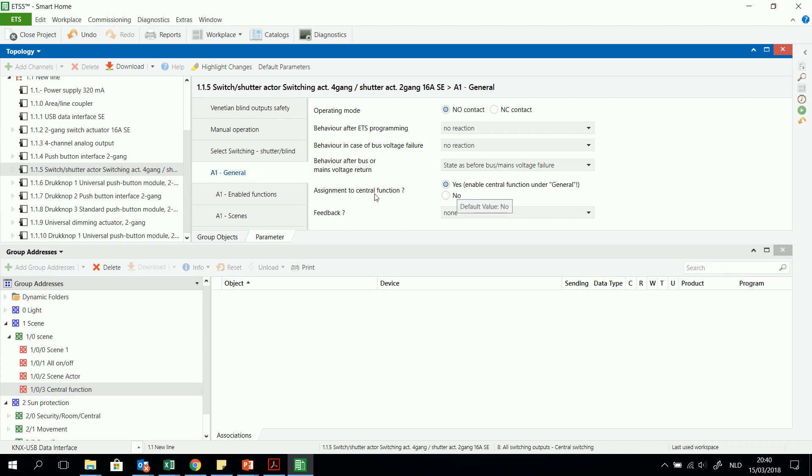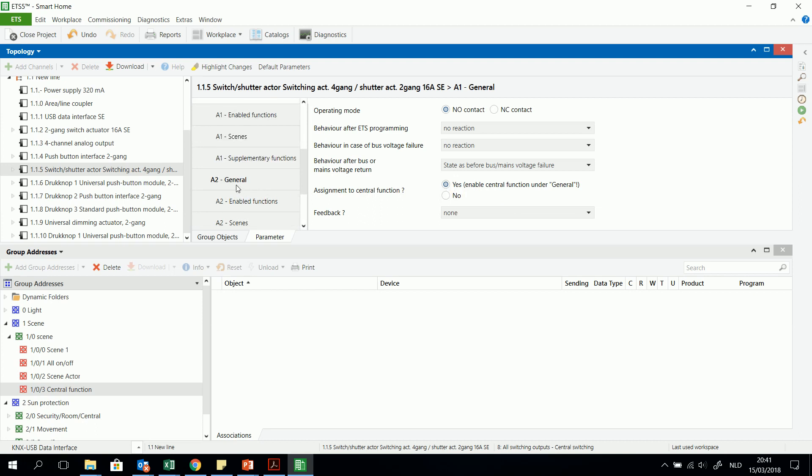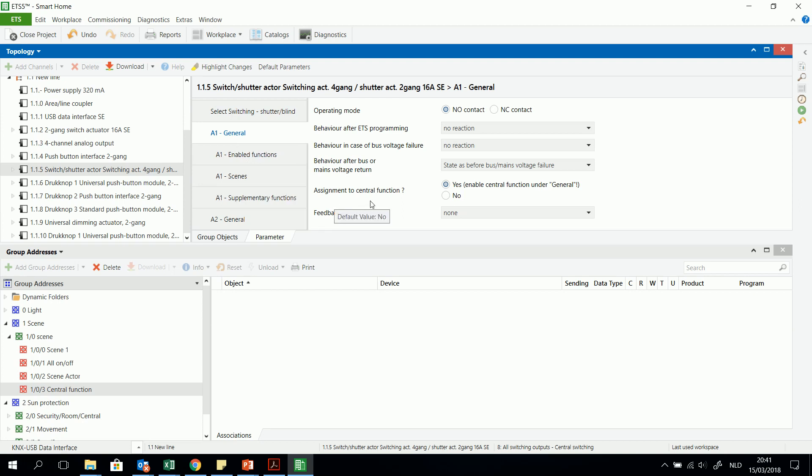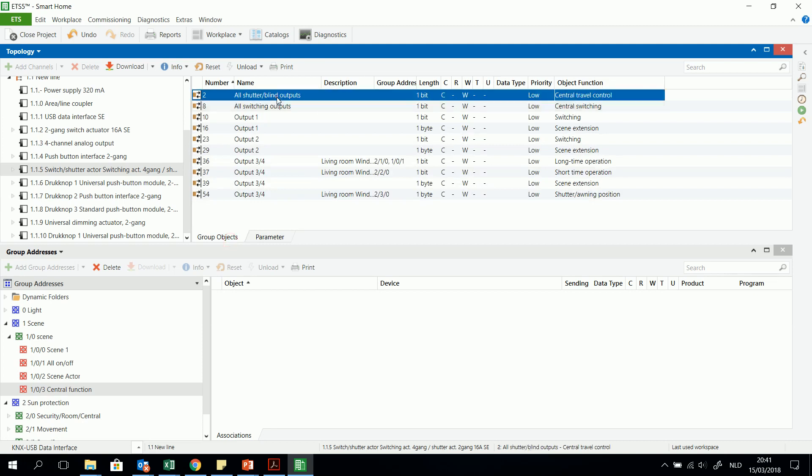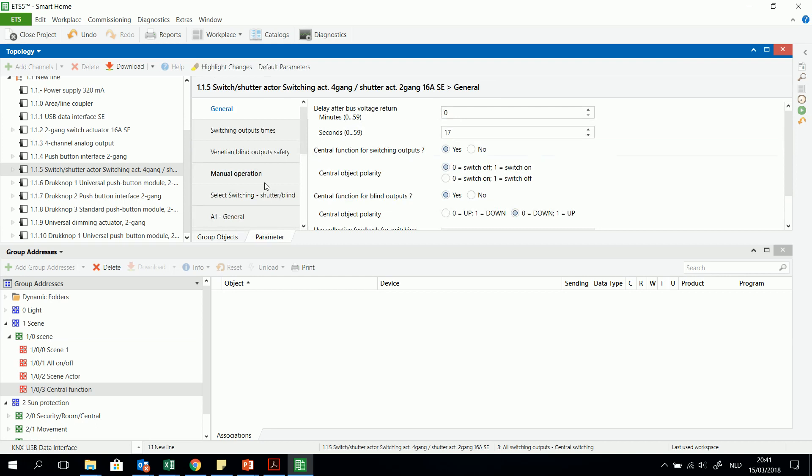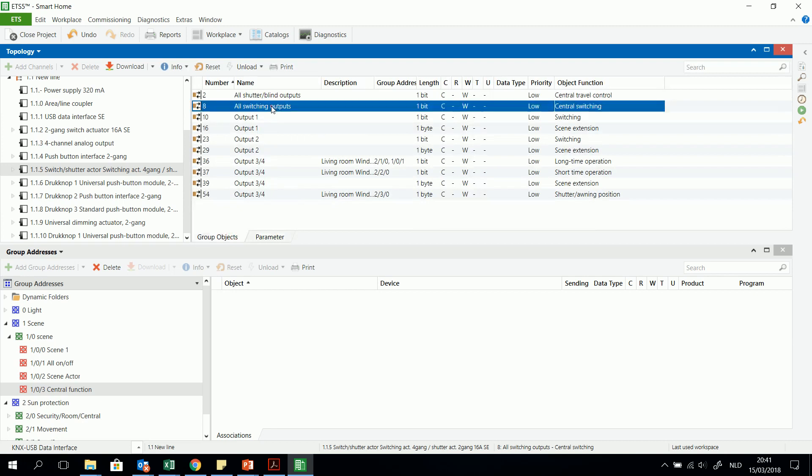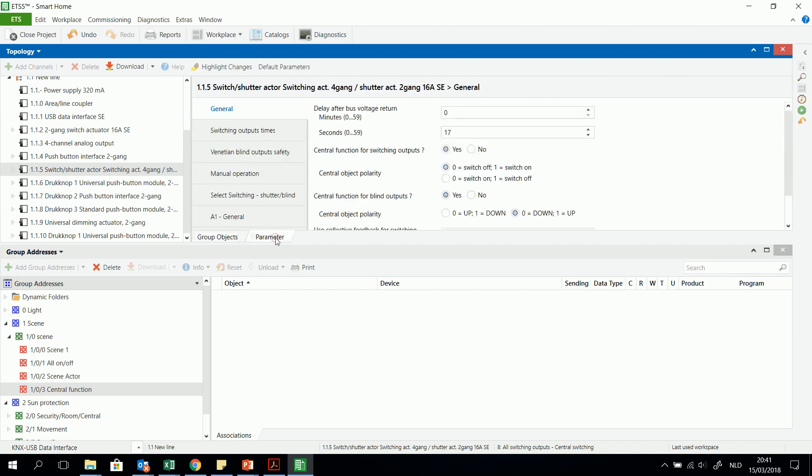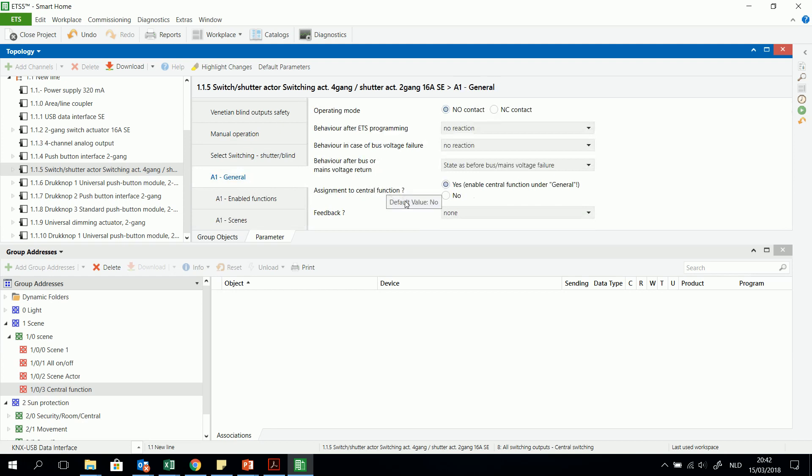So I will assign it now to the central function. This means also that you can choose for a central function not to activate or assign all outputs. For example I have an actuator of twelve outputs, and with my central function I won't use the one bit all switching output central switching object to activate all my outputs. But I can choose which one. I don't have to take all the outputs. I can choose to send only to ten outputs a switching off or on command. Even if I receive to the central object only one bit, so I receive one bit and it will send an on or an off to all outputs who are assigned to the central function.